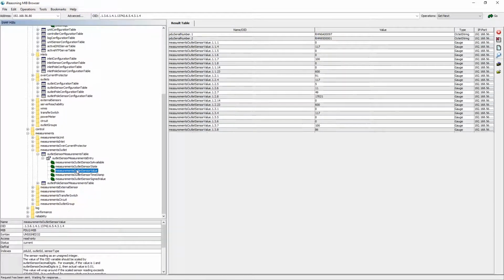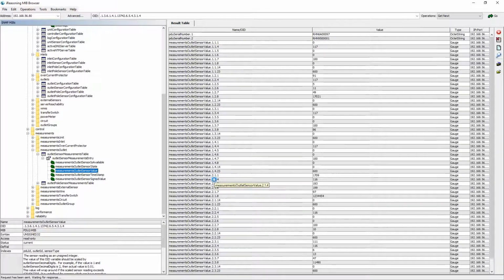So I have this PDU ID index that's now available, and it shows me the serial numbers of these two PDUs. The same thing applies when I want to look at an outlet sensor value. You'll see I get my 4 outlets for my primary unit, and my link unit is down here. That first integer is my index, so that's PDU2, that's where that ID comes into play. If you wanted to set a specific ID for the link PDU, that will come into play there. If you're using any external tools, just make sure you test it and make any changes needed on your SNMP management server to support that.